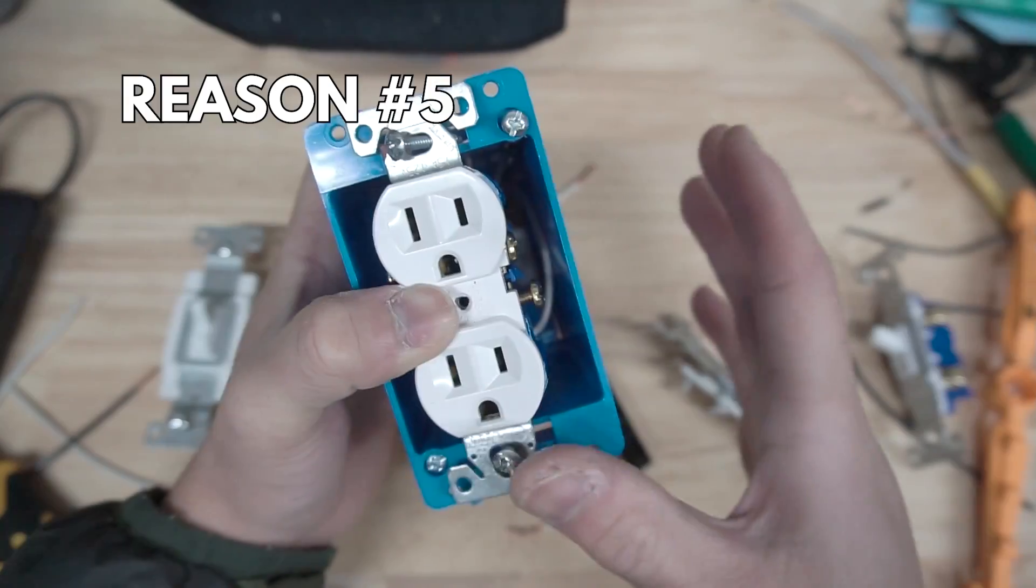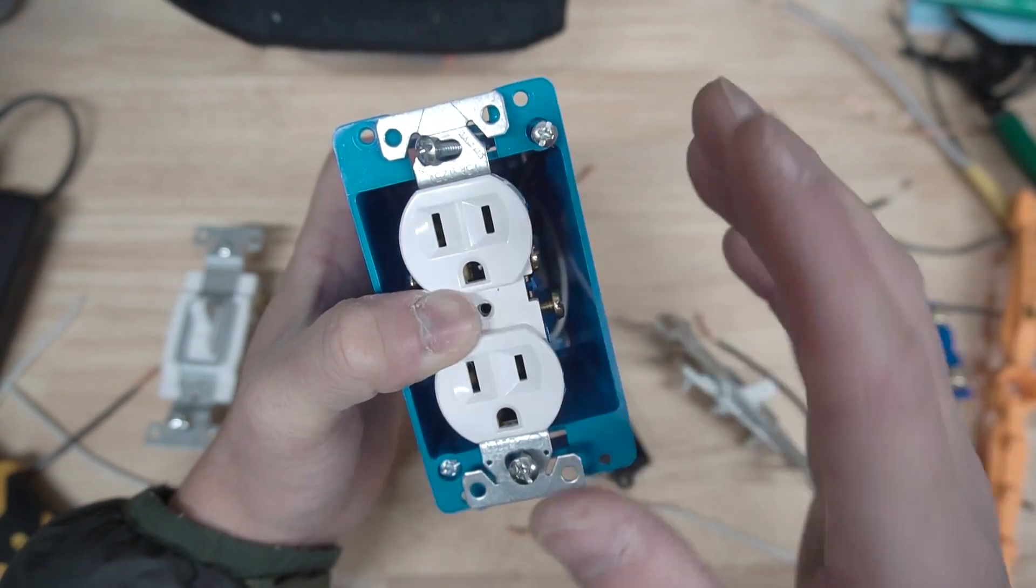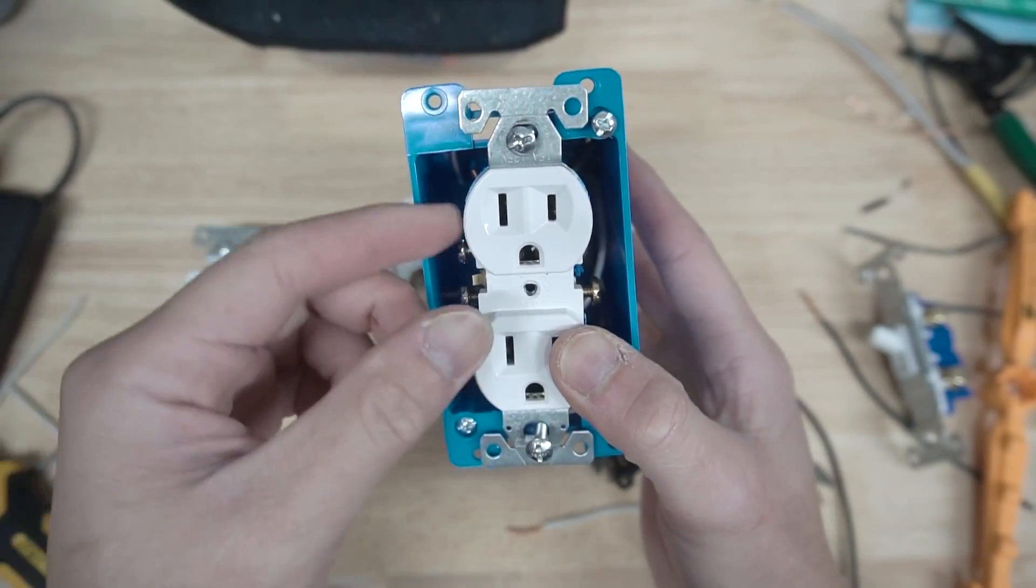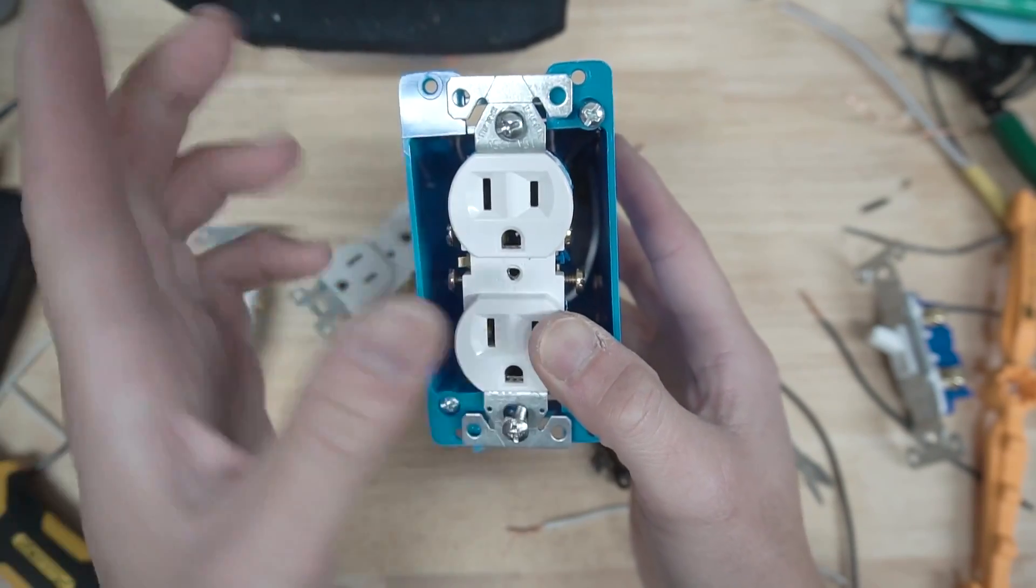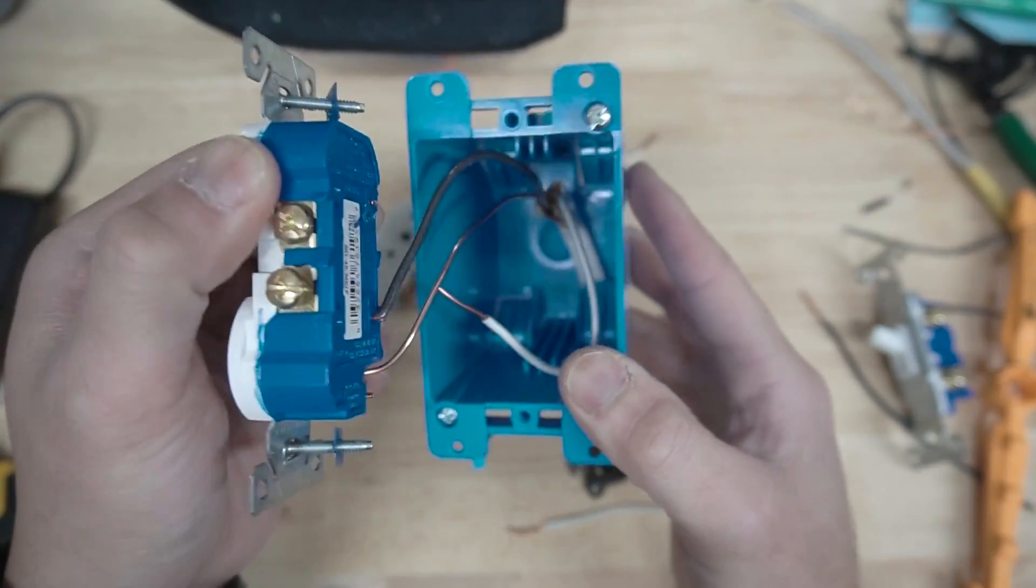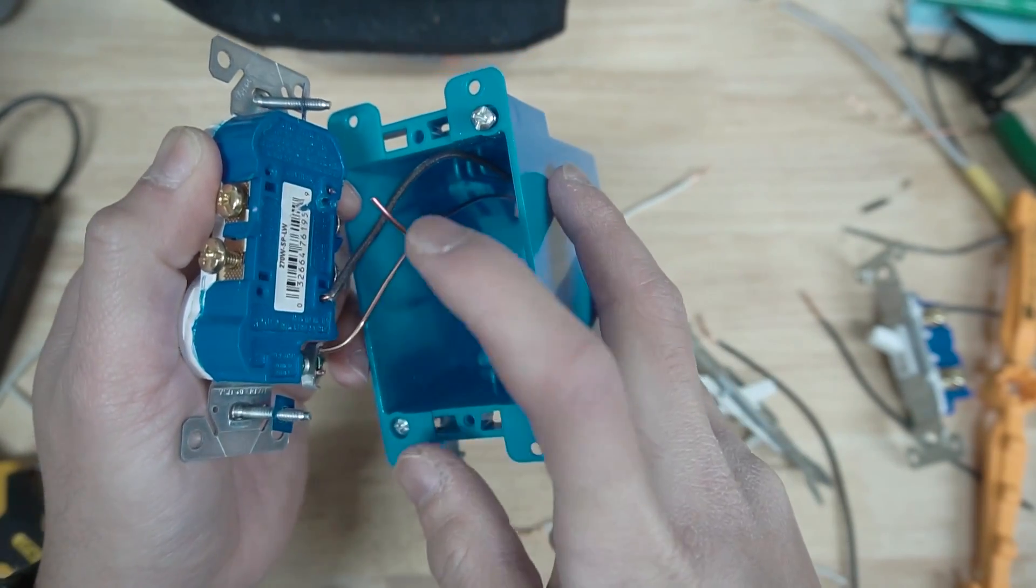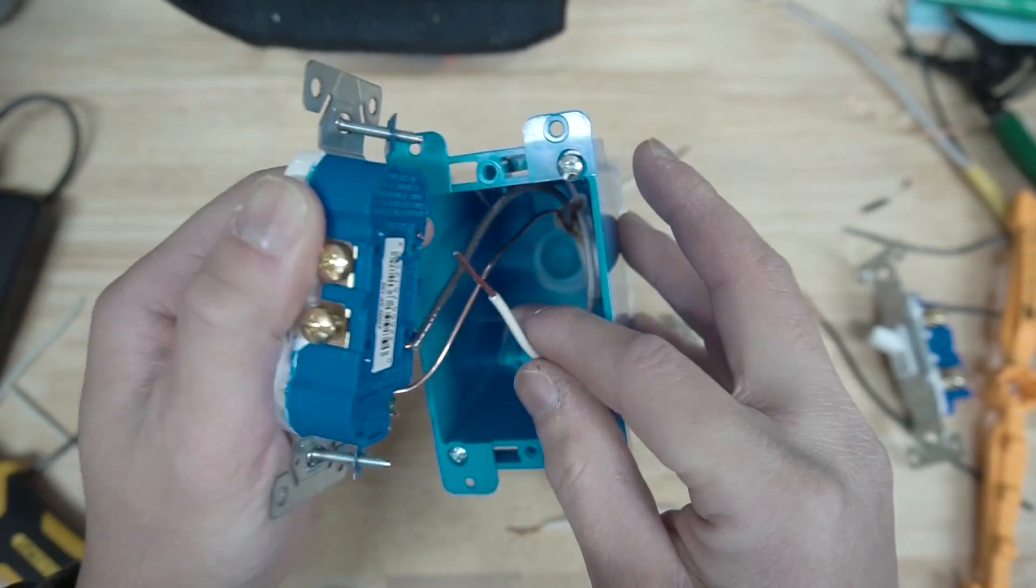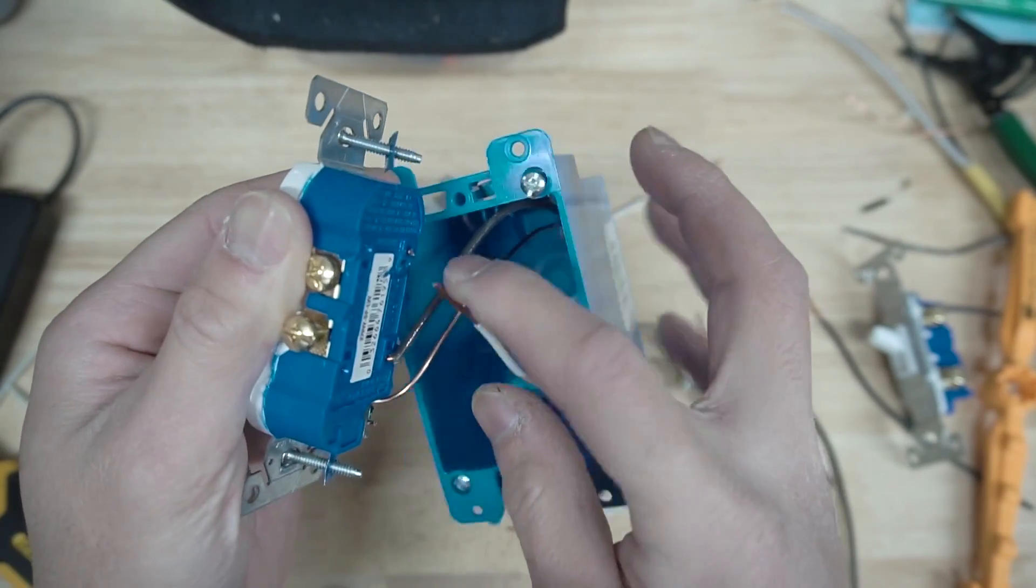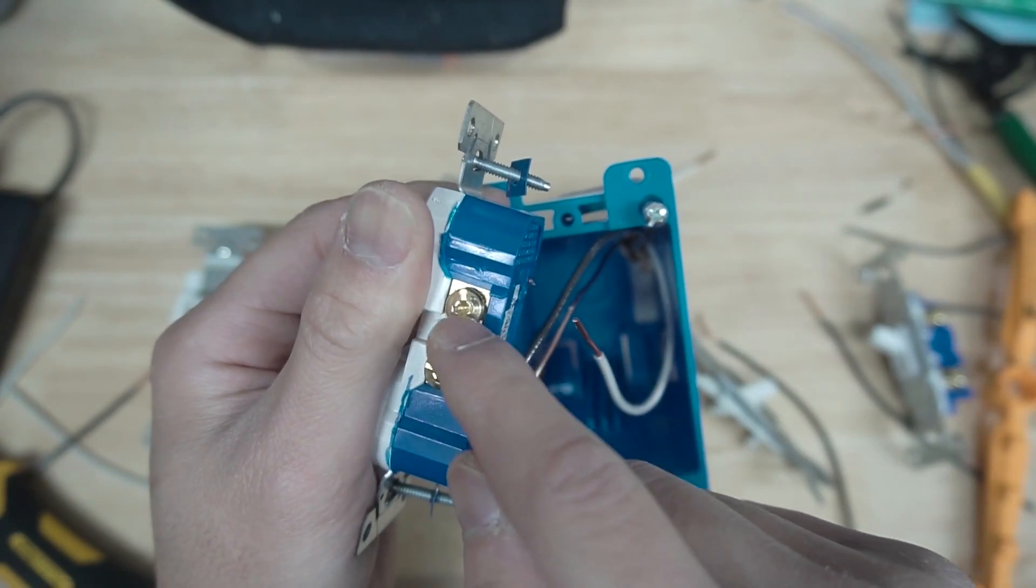Reason number five, the final one why I don't recommend speed wiring: here's an example I come across many times. When I open up a junction box and take out the outlet or especially the switches, and I try to pull it out, you have a wire that is just sticking out there, whether it be neutral or hot. I've come across it, and it is really dangerous. That's because the speed wire method has failed.